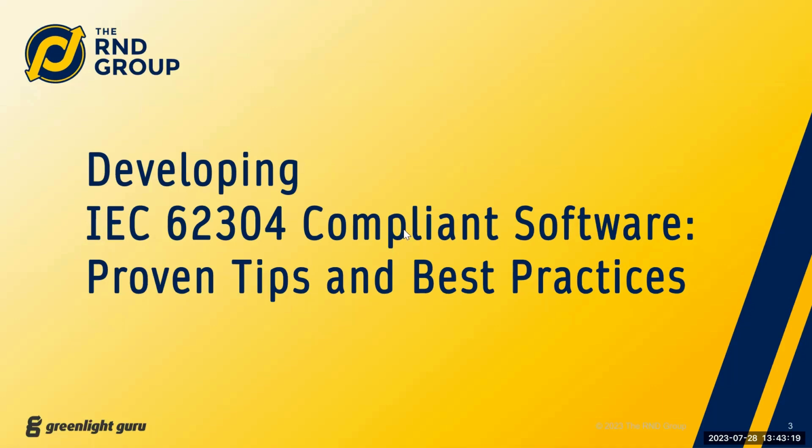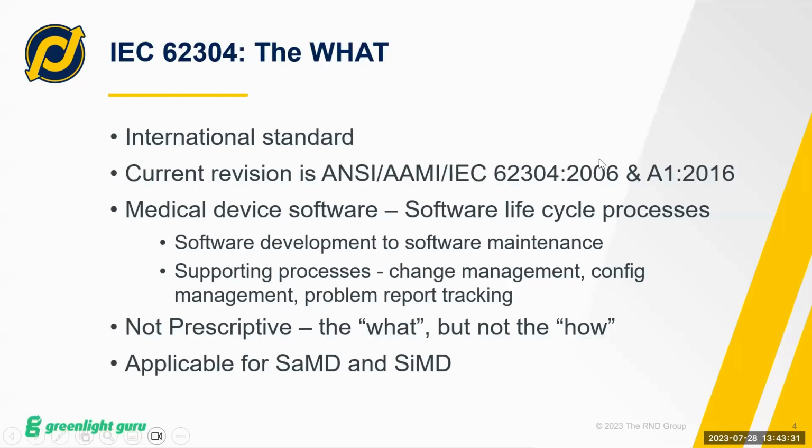All right, so like I said, our topic today is developing IEC 62304 compliant software, proven tips, and best practices. IEC 62304 is an international standard. The current revision you can see there is an amendment. It actually was 2015, but 2016 is when it was adopted by the other organizations, ANSI and AAMI.